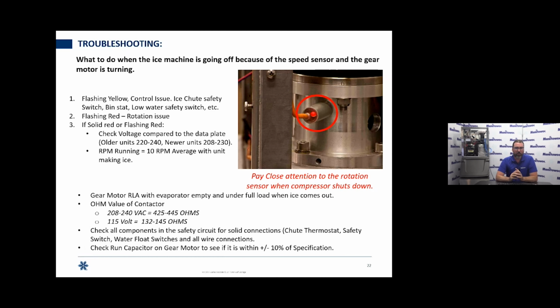You can put a paper clip in there that will bypass the rotation sensor startup delay period. Or we can just wait the 8 minutes and see if it does go straight to solid yellow. If it does, okay, we don't have a problem. We can probably just move on with our day. But if we start to see flashing red, we definitely have a rotation issue.